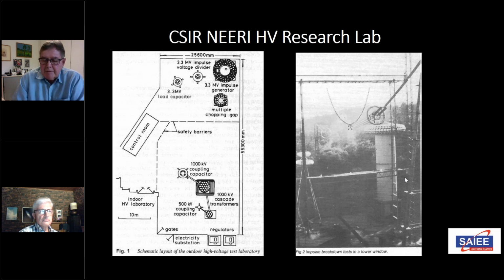We were able to do important measurements on long sparks here, under altitude conditions of 1450 to 1500 meters, because air density correction factors were not well known at that time for engineering applications. Henry and his team also extended this into studies of long spark physics, photographing the leader and streamer development in the long spark. So it was a nice consolidation between the lightning studies and the engineering design applications for very high voltage, and how the physics of that works.